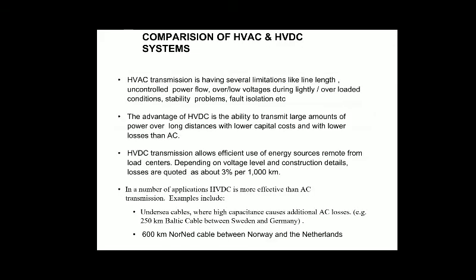Here is a comparison between HVAC and HVDC systems. HVAC transmission has several limitations like line length, uncontrolled power flow, over or low voltages during lightly or overloaded conditions, stability problems, and fault isolation issues. The advantage of HVDC is the ability to transmit large amounts of power over long distances with lower capital cost and lower losses than AC. Losses are quoted as about 3% per 1000 km.